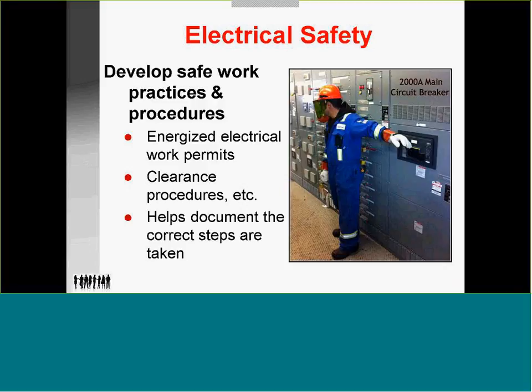Safe work practices. If you notice in the photo here, this gentleman is turning off a 2,000 amp circuit breaker. Now just back to it. Using the left hand, in the event of an explosion, it will turn him away from it and pull out of the way. If he was doing right-handed, he would turn into the blast, cause significant injury. So a left-handed rule is another way of doing it. This is in a Category 1 outfit.